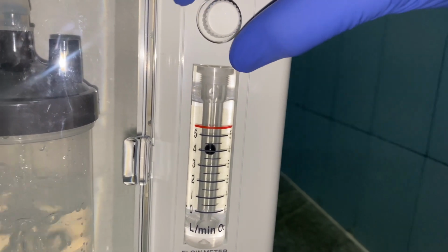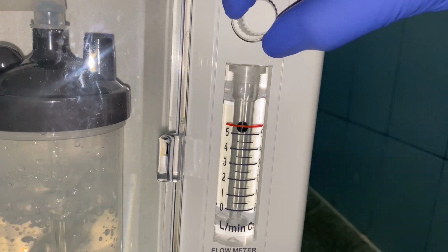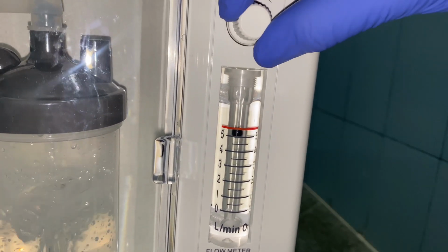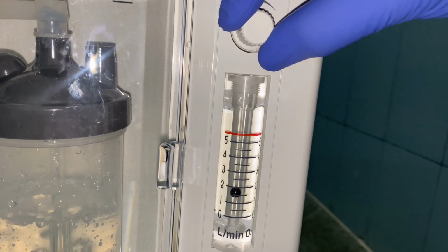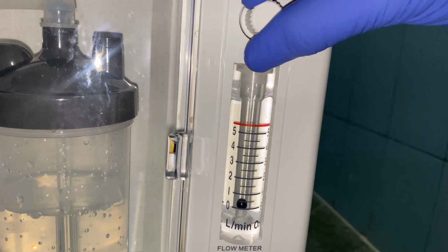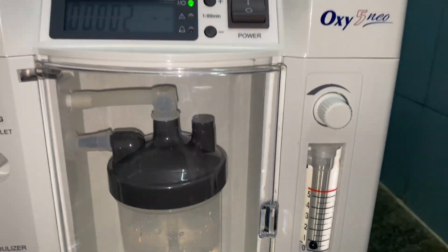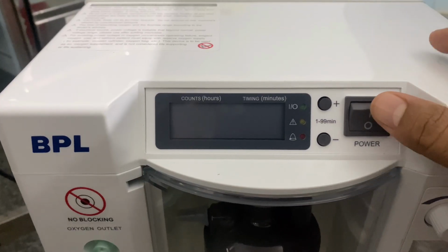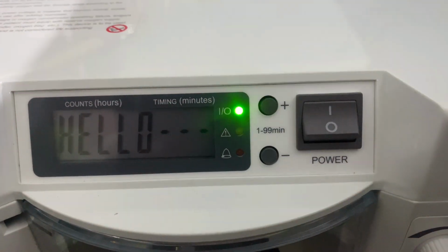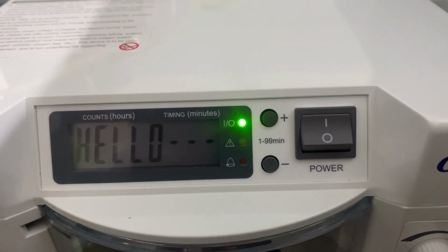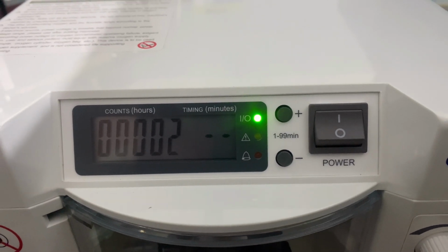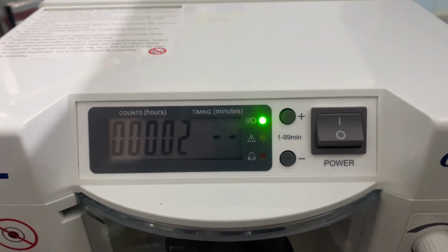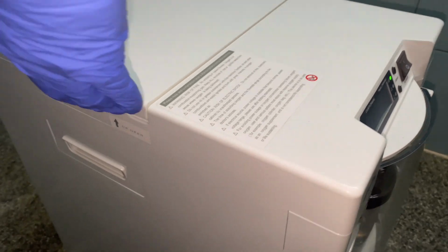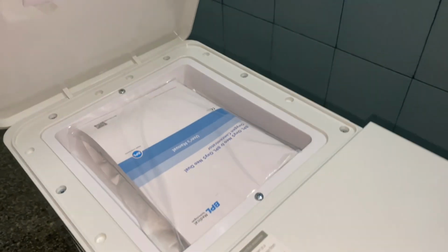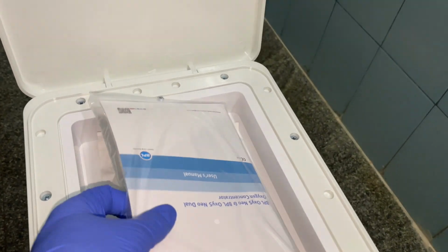Here there is a knob to adjust the flow rate, that is in liters per minute. You can adjust 0.5 to 5 liters per minute. As I told, there are three lights here: green, yellow and red. Green indicates the system is in good working condition. If the yellow light starts blinking, it indicates that oxygen concentration is greater than 50% and lesser than 82%. And if the red light starts blinking, it indicates the failure of the system.